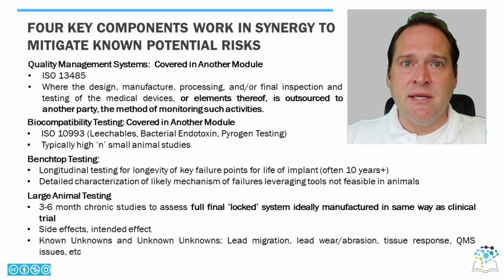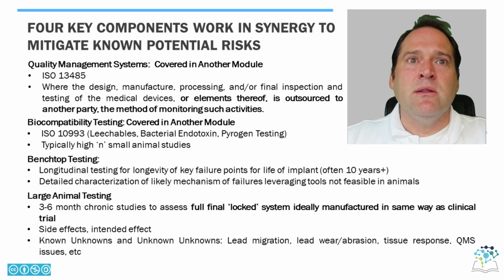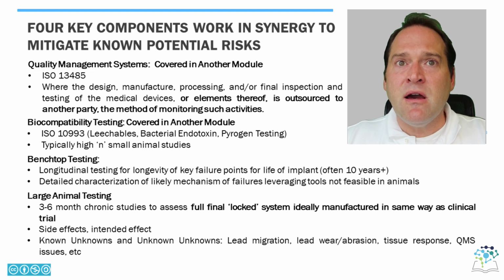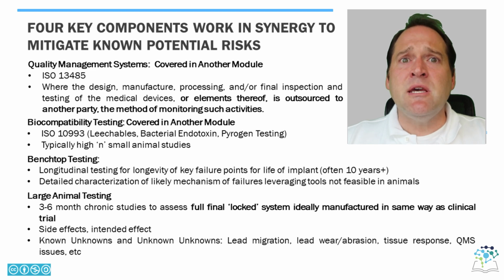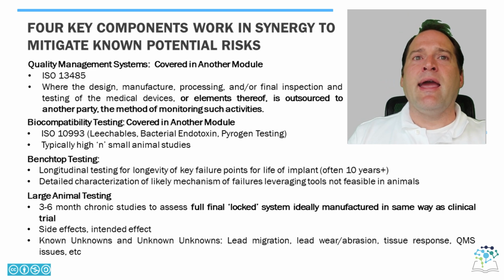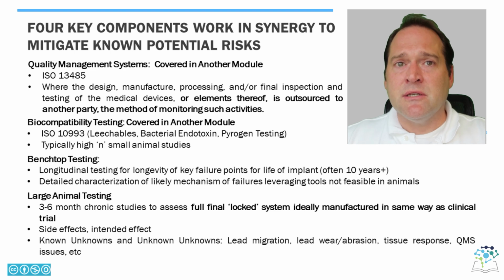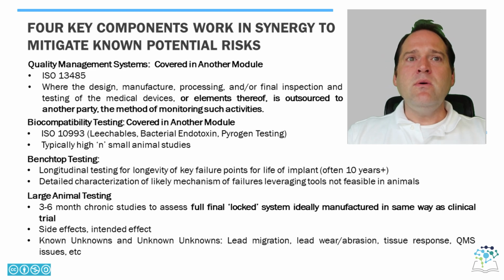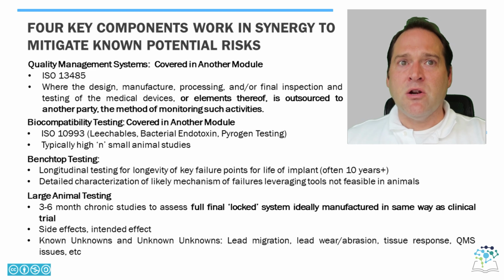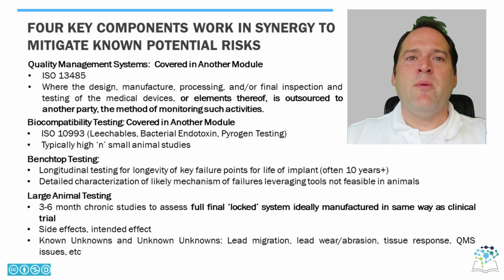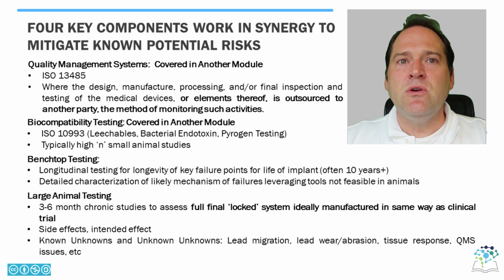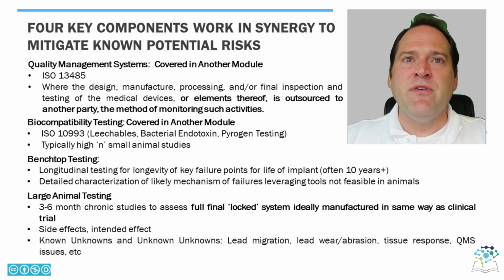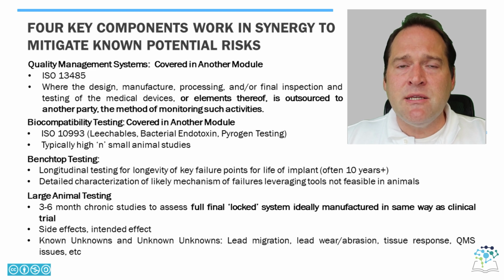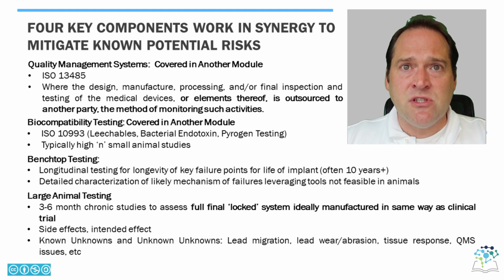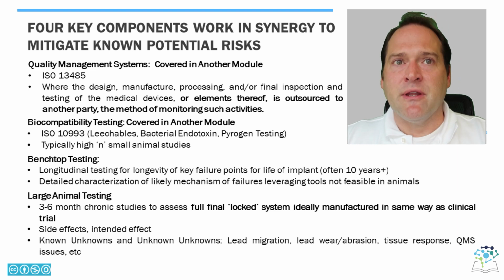Second is biocompatibility testing. This is taking a passive implant and looking for things like leachables, bacterial endotoxins, and pyrogen testing. This is typically done in small animals so you can get to high n and do some really nice statistics as part of the evaluation. Then you have both benchtop testing and large animal testing, and they have different goals. The benchtop testing is really your longitudinal testing for longevity of key failure points for life of implant. Now, for an implantable, you're typically shooting for 10 years, sometimes 5, in terms of device longevity.